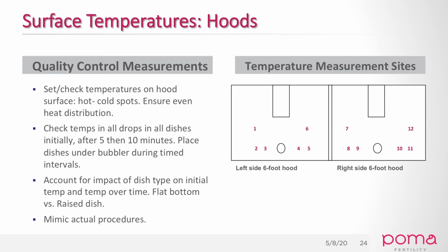The slide here on the right will show the template of, for example, a 6-foot hood. So when we go to start QC, we check all the places in the hood where people would potentially put dishes, and then we actually go through mock procedures. And I've given some suggestions here at 0, 5, and 10 minutes. You want to place the dish under the bubbler because you want to actually recreate the events that you're doing. And the reason why this is really important to do is because a lot of us use dishes with different architecture on the bottom of the dishes. So some of them have flat bottoms and others have raised bottom dishes. And so that's actually going to impact temperature much more than you think. So the take-home message here is really mimic the procedures that you do in the lab.